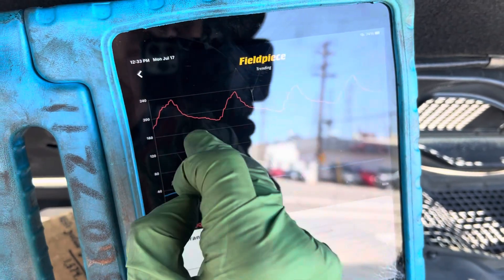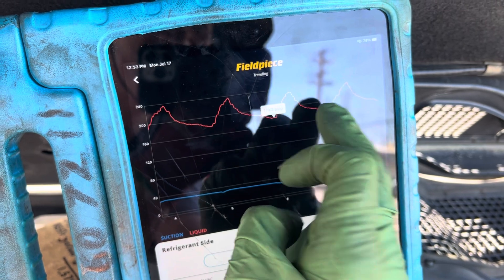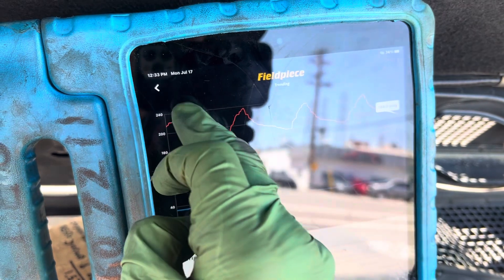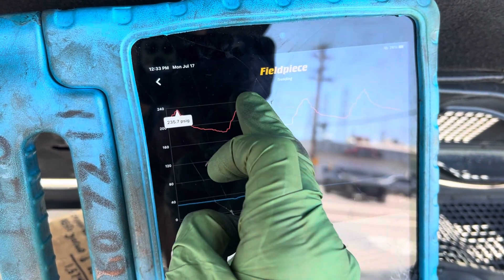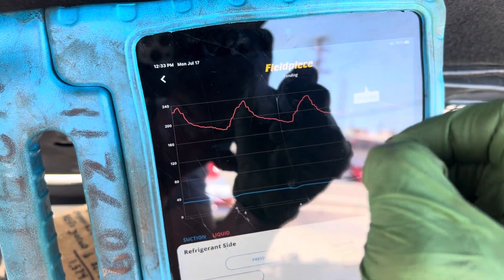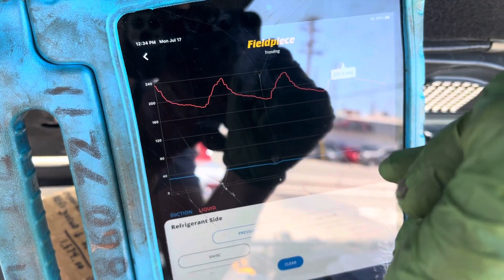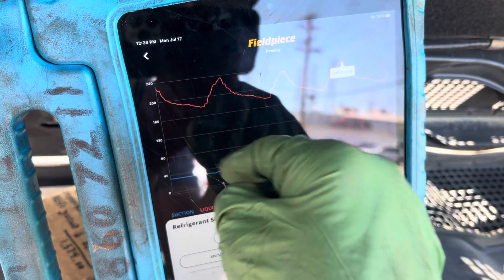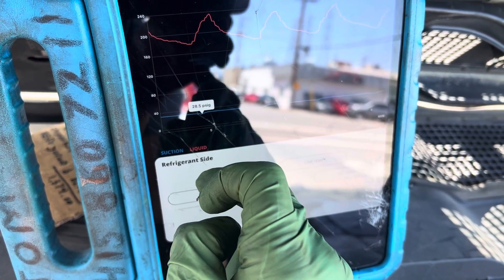Here's the pressure swing: our high side is going from a low of about 179 psi back up to about 240 psi — actually it hits about 240, but there's a little time delay between what the pressure sensor picks up and what it's actually doing. That swing happens about every 45 seconds. On the low side, it barely dips from 30 to 28 psi — so 28 is the low on the low side.